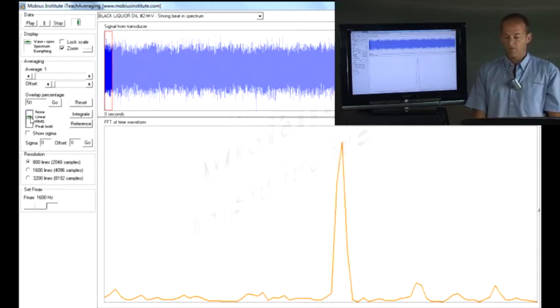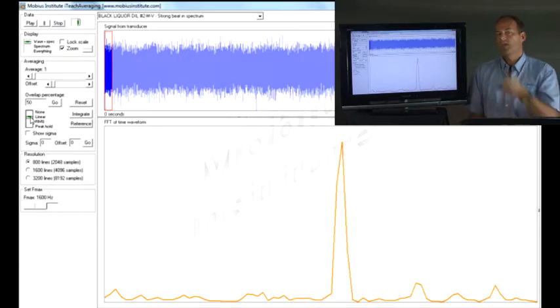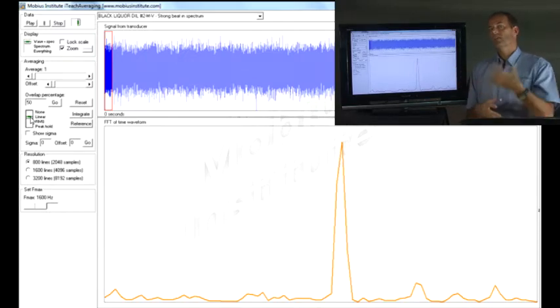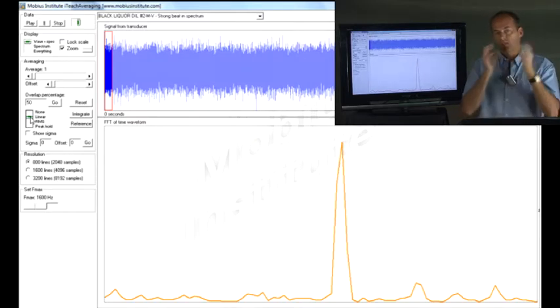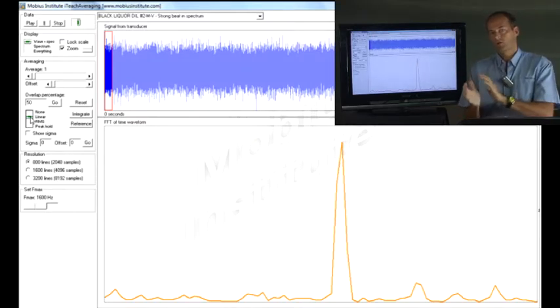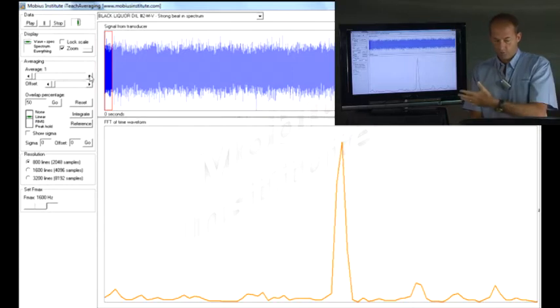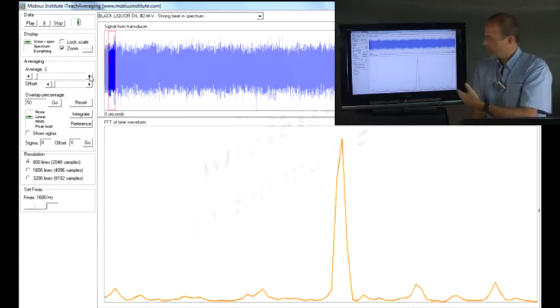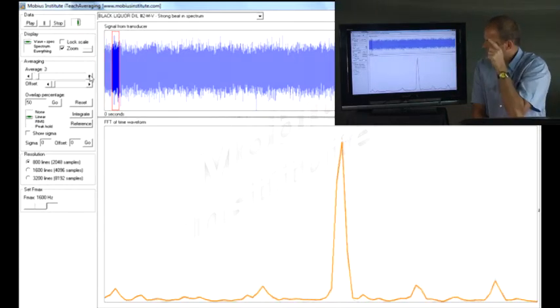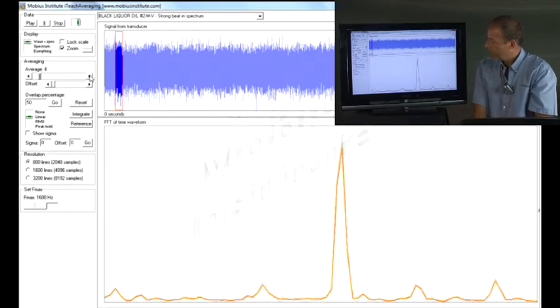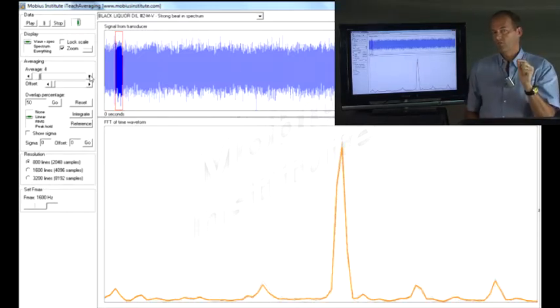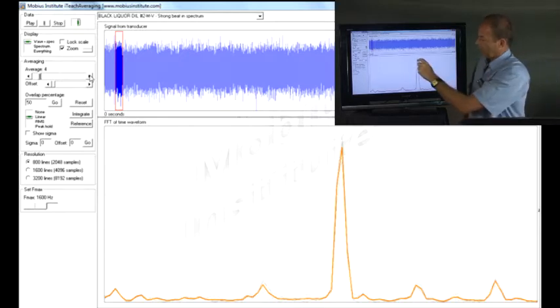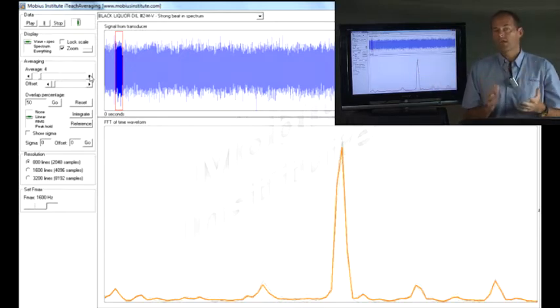I'm going to turn the average option on. The light gray spectra you see will be the individual spectra that the analyzer collected. The orange is the average. So there's first average, second average, see that didn't vary very much, third, fourth. Now notice that if we took four averages, we would get that spectrum there and it looks great.